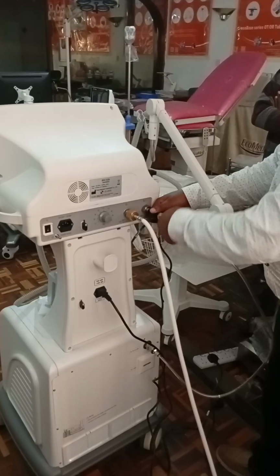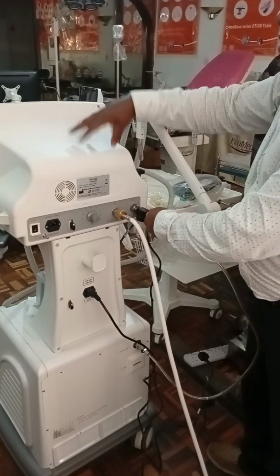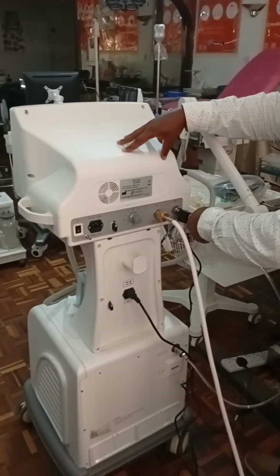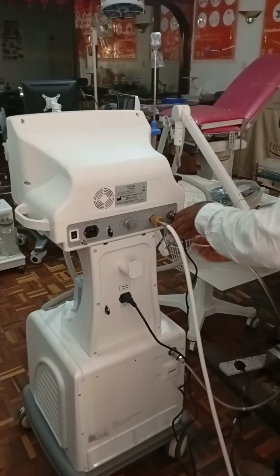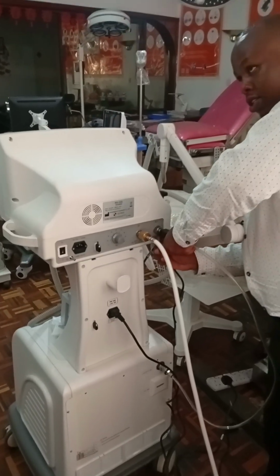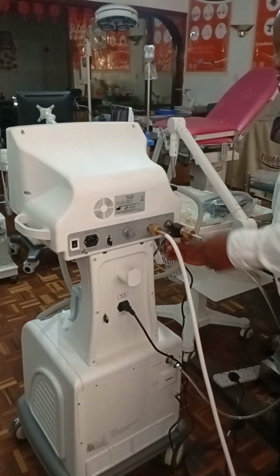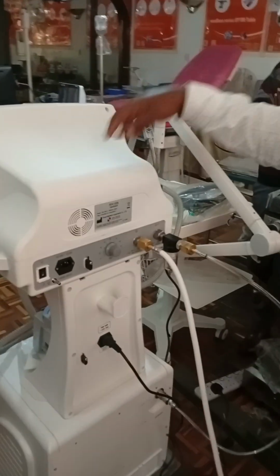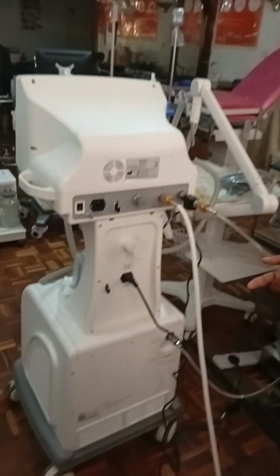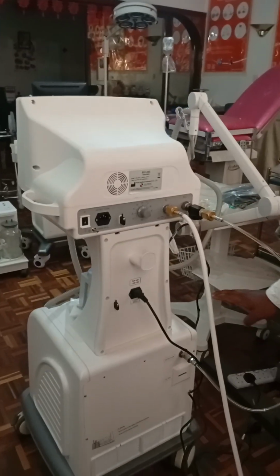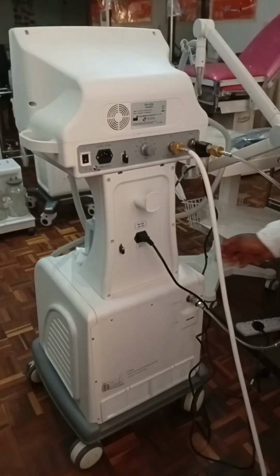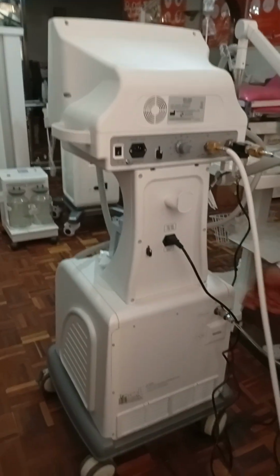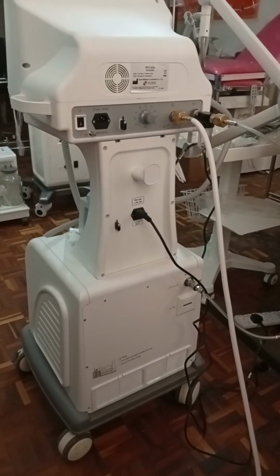For our ventilator, the upper part, it has a backup battery which can stay up to 72 hours without draining. But you'll keep checking because the display will indicate the battery percentage so that you keep charging. But the compressor part doesn't have a battery. So for you to operate the compressor, you need to connect to power.